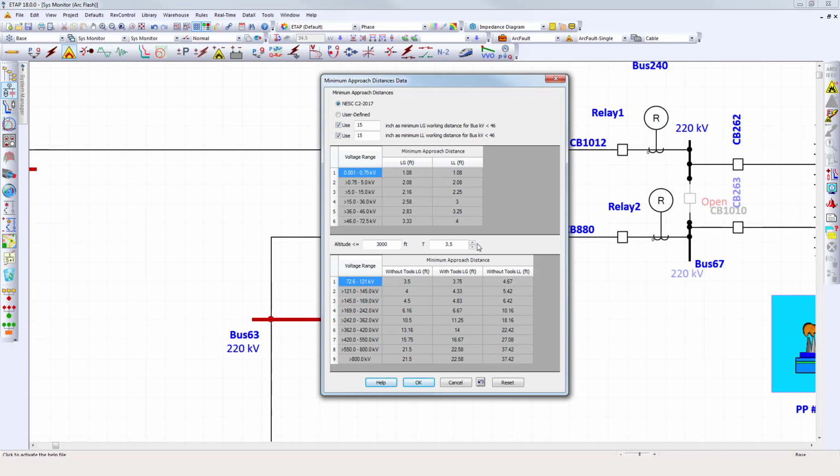What's really important here is to also recognize that these distances vary as a function of the transient over voltage conditions which could occur, and it's very common in distribution and transmission systems. Sources of transient over voltage conditions include lightning, the operation of protective devices as loads are added or released from the electrical grid, and so forth.